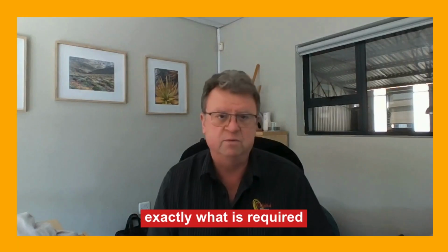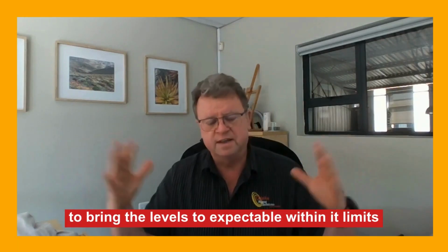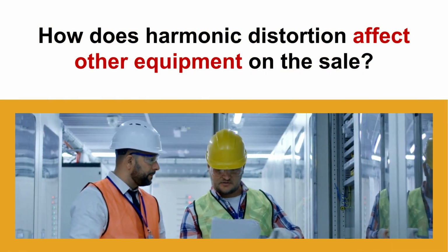The other thing I wanted to add is that it's not necessary to eliminate or neutralize harmonics completely. A certain level of harmonic content is totally acceptable. There are very strict rules about what conditions and levels are deemed acceptable and not dangerous to electronic equipment. Fixing or reducing harmonic levels can be an expensive exercise, so the trick is to find out exactly what is required to bring the levels within acceptable limits.